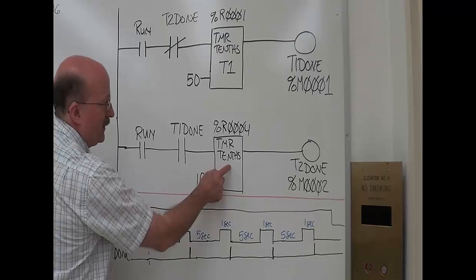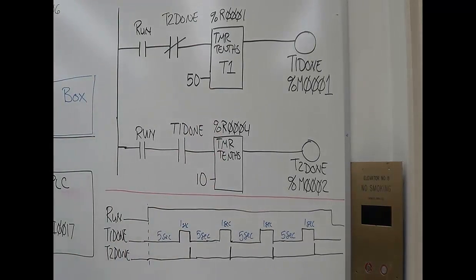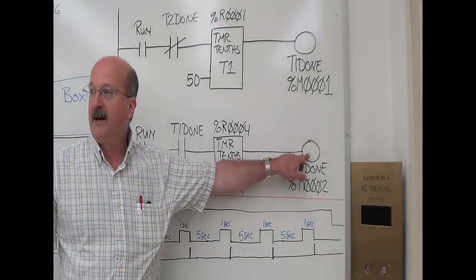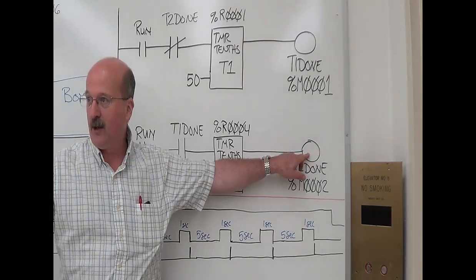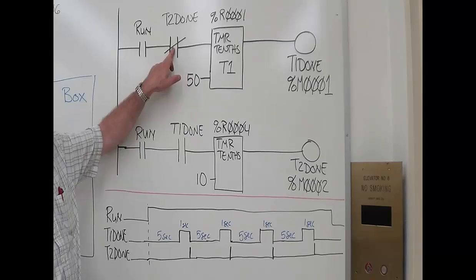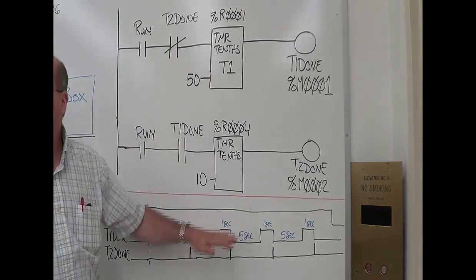So your output, these are both on delay timers. T2 done is not a one-shot coil, it's a standard coil, but it's effectively a one-shot coil because this will come true. The next scan, this will open up, reset the timer, and shut everything off for one scan.